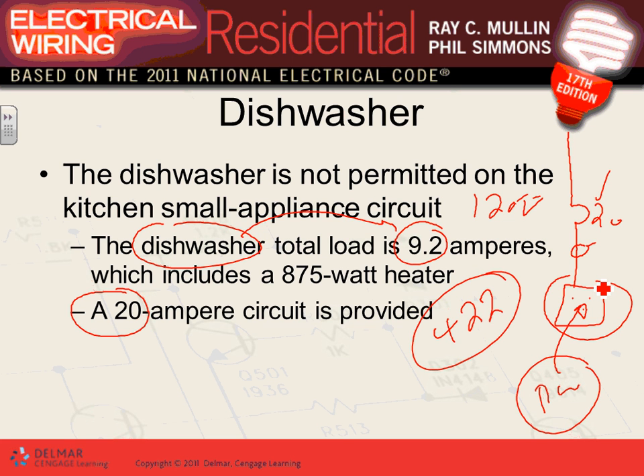when you do. You require an overcurrent protection device, number one. Number two, require a feeder. Number three, require a disconnect. Number four, typically a controller. And five, an overload. So the controller and the overload, a lot of times for appliances, are provided by the manufacturer, so we don't worry about them. So these two, the controller and overload for the dishwasher, are built right into the dishwasher.